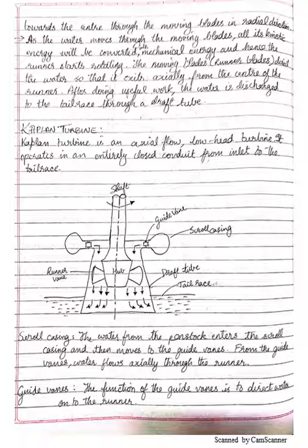The main thing is the placement of the guide vanes and the runner vanes here, which is different. As you see, through the scroll casing the water comes and gets shifted by an angle of 90 degrees, and then strikes the runner vanes. After striking the runner vanes, it moves through the draft tube and goes out into the tail race. The scroll casing here is the passage through which the water changes its direction. From the guide vanes, the water flows into the runner. The guide vanes direct the water onto the runner.